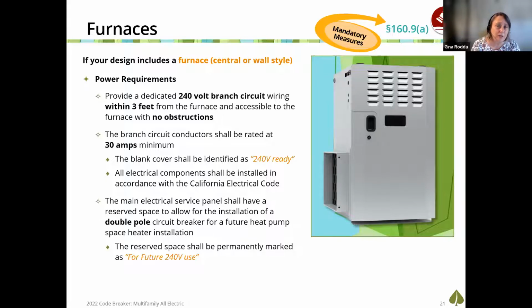That's pretty beefy. And you have to make that branch circuit in the electrical panel serving this particular electric ready area reserved for a future 240 volt appliance. At the main electrical panel serving this area or this dwelling unit, you will additionally have to reserve a double pole circuit breaker for this future 240 volt service to the appliance.